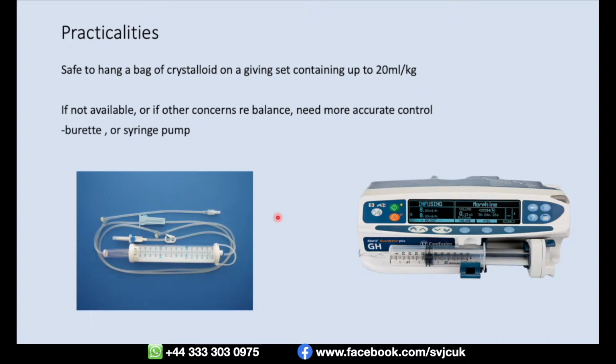Once we get down to neonates, we're going to be looking at using syringe drivers. So if you're trying to give, like we saw before, perhaps 14 mLs per hour to a neonate, then it's really hard to do without something like a syringe driver.